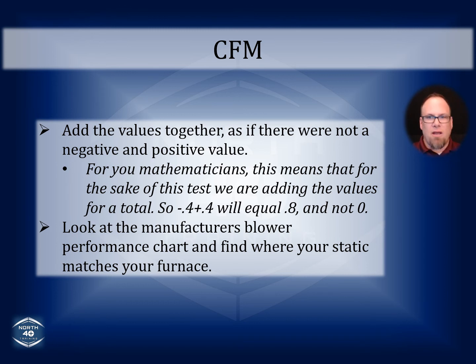Looking at the CFMs, again, when you're taking your CFM static measurements, you're dropping the negative and the positive off, and you're adding just the raw numbers. So like I said, negative 0.4 and positive 0.4, traditionally in mathematics, that would equal 0. But in what we're talking about, you're taking the negative and positive, throwing it on the floor, and adding the raw numbers, which would be 0.8 in this particular instance.